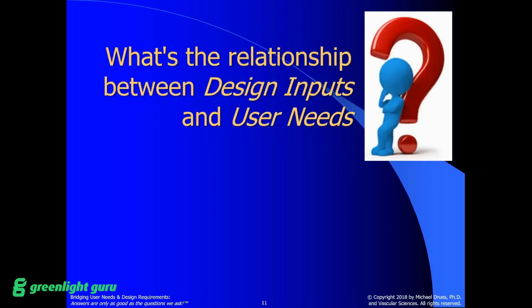Typically, we collect our user needs first, and then we translate those to design inputs. And I found it interesting in the polling question that I shared at the beginning of the webinar. If I remember the statistics right, about a third of the audience said that those user needs were generated internally within the design group. With all due respect, that's wrong, because unless you are using your device yourself, if you're not the intended user, then how can you come up with a user need?